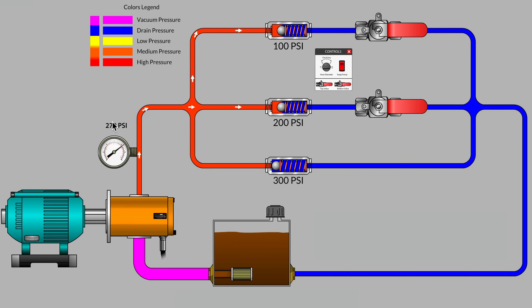But where did the 79 part come from? Well, at this point, it's a bit of an arbitrary number, but it's safe to say that that 79 psi is resistance that has been added to the system pressure because we've gone to a much larger pump without upsizing the diameter of hydraulic tubing that we're using on these branches. So now it's evident that the diameter of the hoses themselves is part of the system resistance, the system pressure that we're seeing on the main gauge.